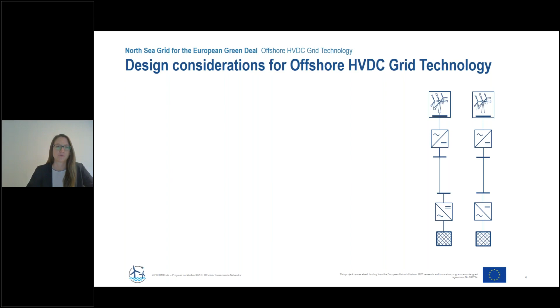Let's first look at design considerations for offshore HVDC grid technology. When moving from the existing point-to-point to multi-terminal systems, we have to discuss system design and normal operation conditions, for example, the DC voltage levels, the DC configuration, the operational strategies, and of course the main point, interoperability of the different components and converters in the grid.